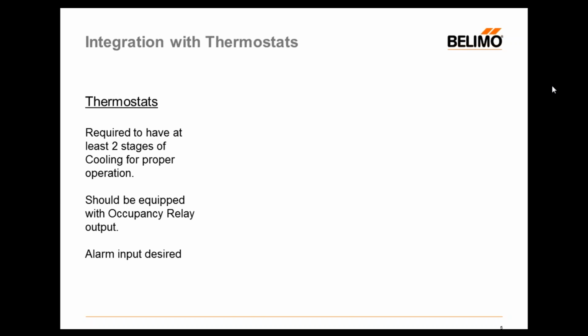If you can find a thermostat with an alarm input, this can notify the occupants of a problem up on the roof. The ZIP economizer has an alarm output that will do that for you. This is actually a requirement in the state of California.